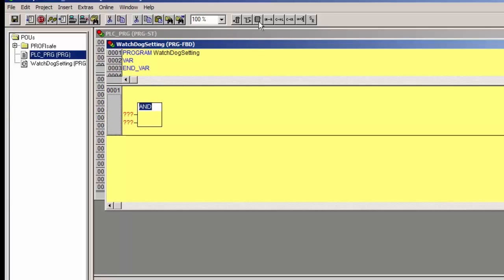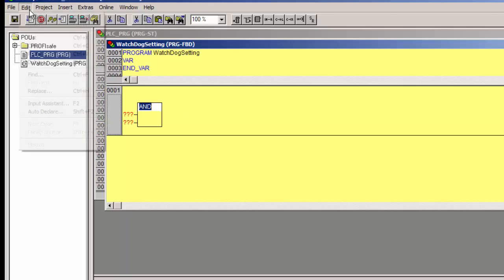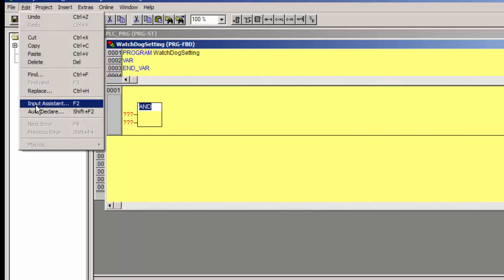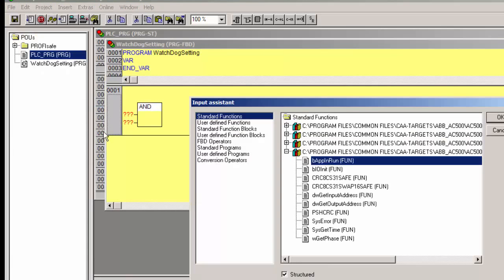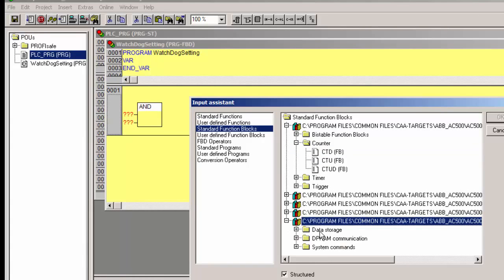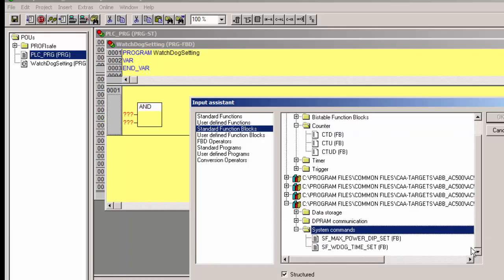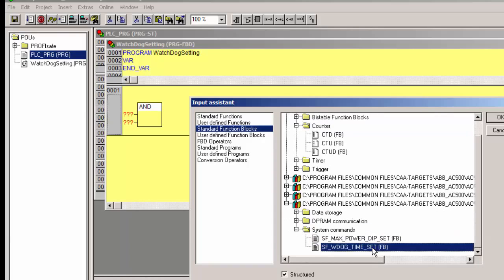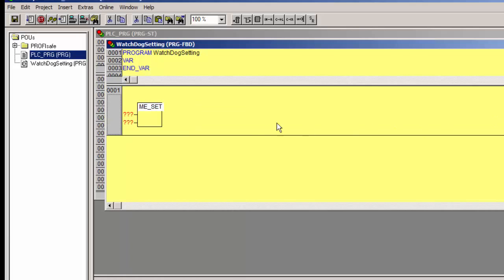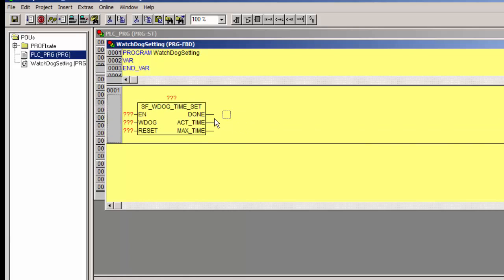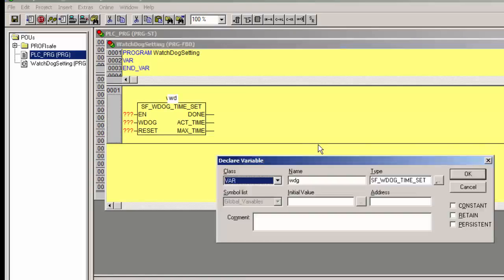Since there is no default watchdog time setting for the safety CPU SM560S, the user has to set an appropriate watchdog value through a standard safety function block. This function block needs to be called at least once, in the beginning of the safety program execution. Without this function block calling, the watchdog time will be assumed as 0 ms and the CPU will go to safe stop mode.